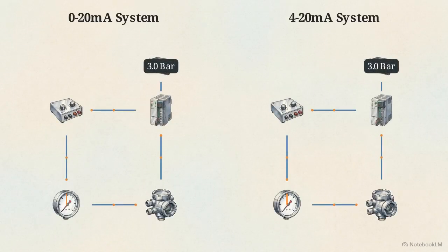This diagram compares a 0 to 20 loop on the left with a 4 to 20 loop on the right. If we cut the wire on both, the current collapses to 0. The 4 to 20 controller instantly recognizes this drop as a fault, while the left dangerously registers 0 pressure.